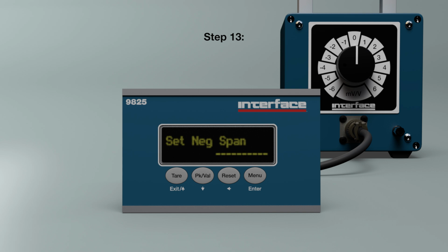Step 13. Once the 9825 has finished recording the fixture value, NC1 will be displayed. For this example, we will use a load simulator to input -4 millivolt per volt. Make sure that the load simulator is set to output -4 millivolt per volt, then use the reset key to scroll through the digits. Use the tare and peak and valley keys to set the NC1 value to 40,000. With the load simulator set to -4 millivolt per volt and NC1 set to 40,000, press the menu key to set the NC1 value. A dashed line will migrate across the display as the 9825 records the input.